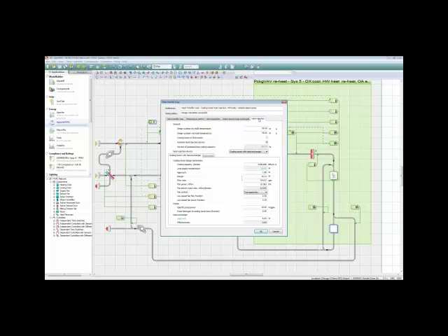However, there's no option for this cooling tower to get in between that heat pump and the coil on the zone side. The coil is connected by a DX, a direct connection to the water loop heat pump, and by refrigerant and not by water.